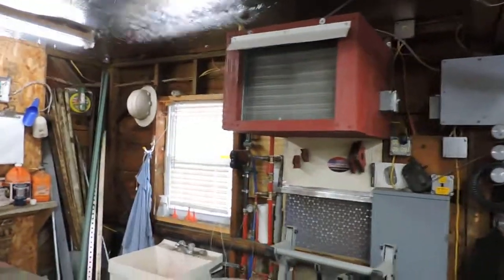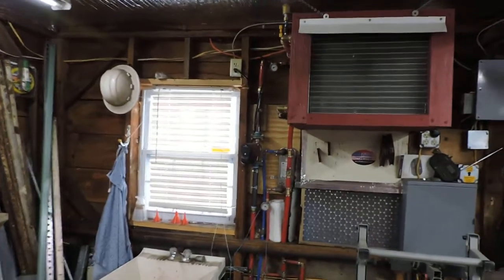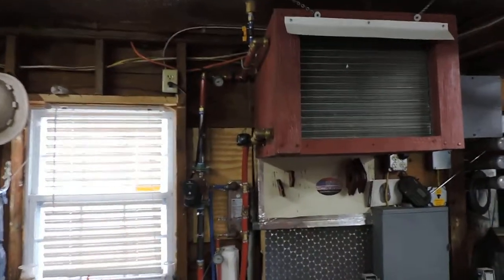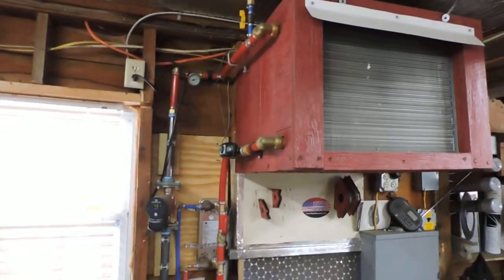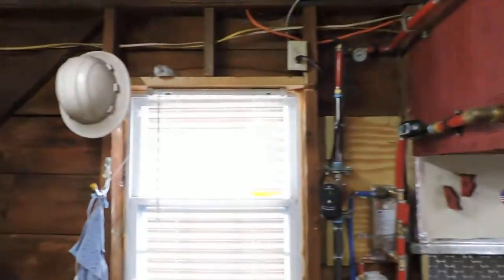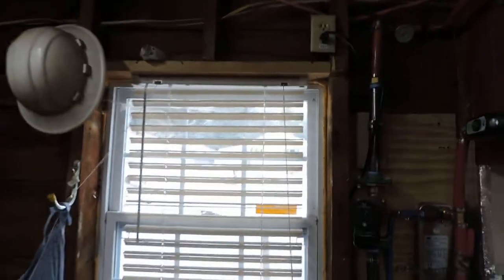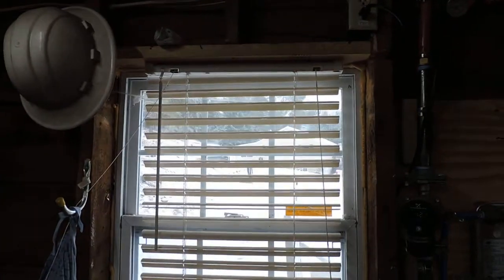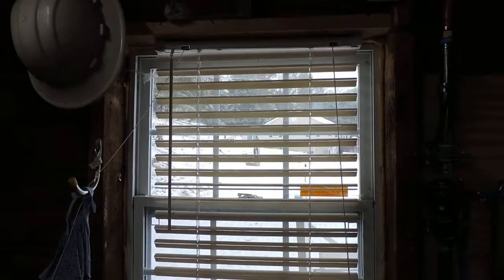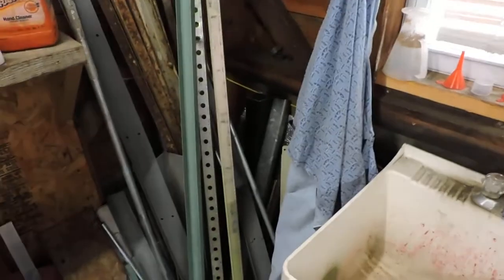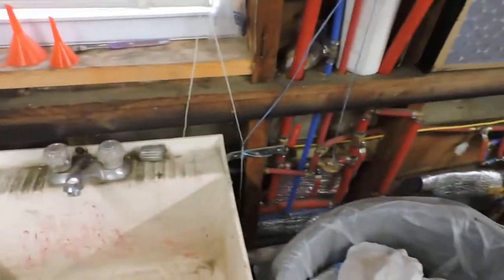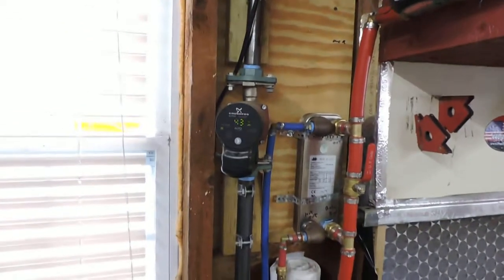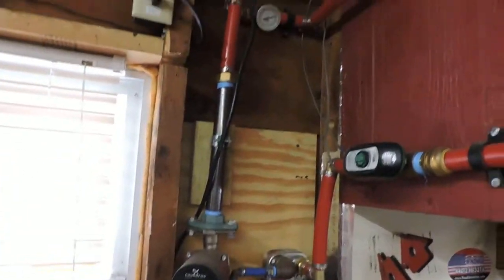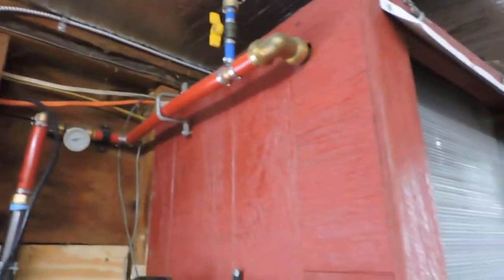Hey YouTube, Hogmeister's Garage. Showing you the hot water heating system we put in here off our wood boiler that's up behind the house. We've got a 175 foot run of 1.25" PEX that comes down here. Once it comes inside the garage, it goes down to 1 inch. Sorry for the mess.